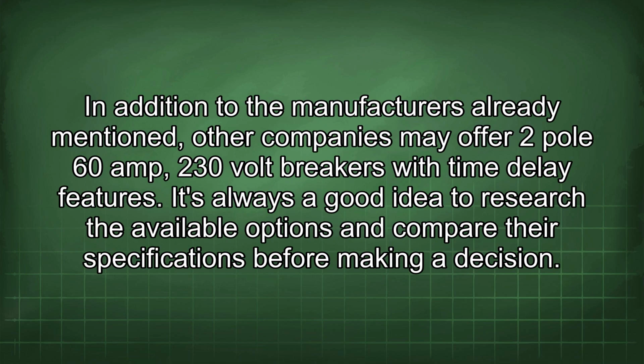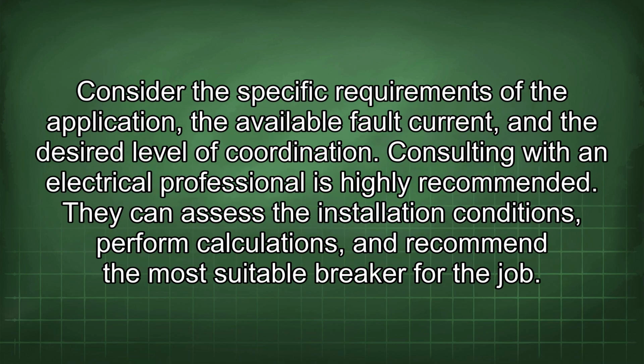In addition to the manufacturers already mentioned, other companies may offer 2-pole 60-amp, 230-volt breakers with time delay features. It's always a good idea to research the available options and compare their specifications before making a decision. Consider the specific requirements of the application, the available fault current, and the desired level of coordination. Consulting with an electrical professional is highly recommended. They can assess the installation conditions, perform calculations, and recommend the most suitable breaker for the job.